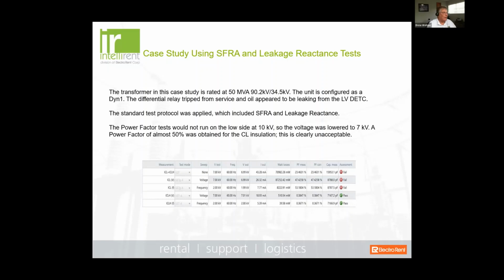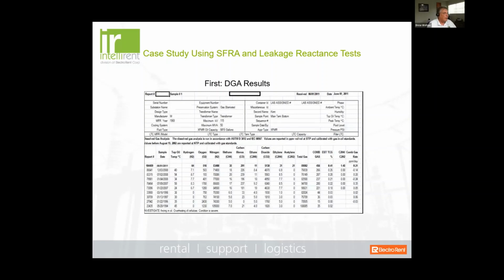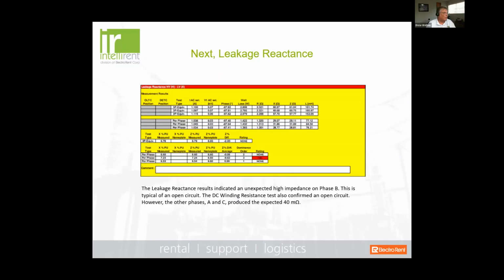Now that is totally indicative of a problem or a failure. Now, subsequently, we looked at the DGA results, and what you'll notice in the DGA results here over time, and we started back in 1994, your acetylene went from 0 all the way up to 21. And that definitely indicates that we've got a problem in the transformer itself. And remember, transformer diagnostics doesn't come down to just one particular test. We want a whole series of tests to get as much information as we can as to what may have happened that caused this differential relay to trip.